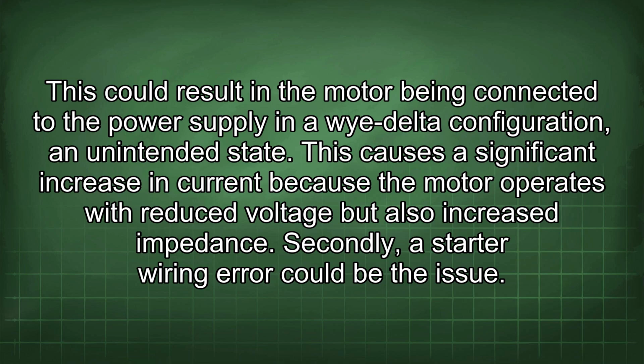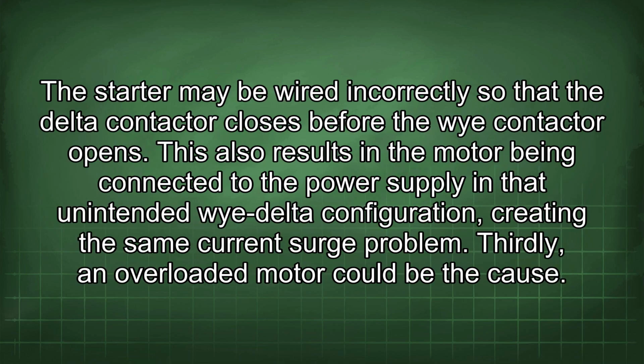Secondly, a starter wiring error could be the issue. The starter may be wired incorrectly so that the delta contactor closes before the Y contactor opens. This also results in the motor being connected to the power supply in that unintended Wye-Delta configuration, creating the same current surge problem. Thirdly, an overloaded motor could be the cause.